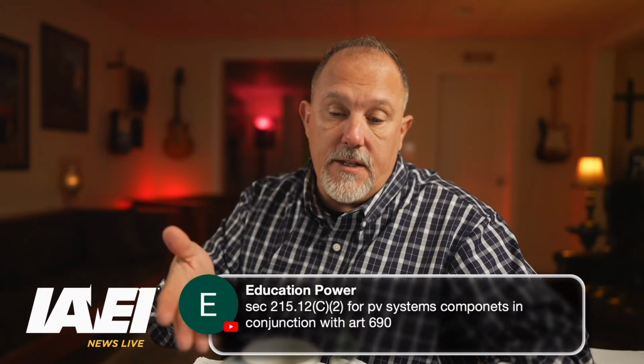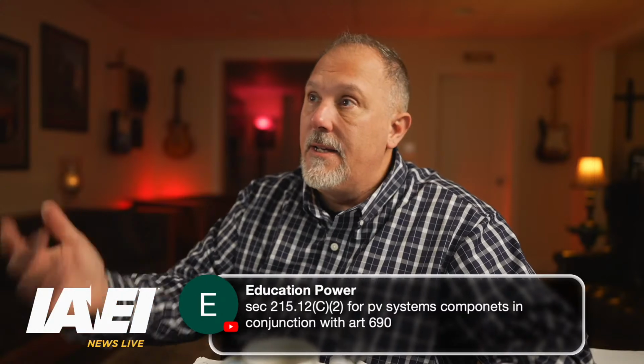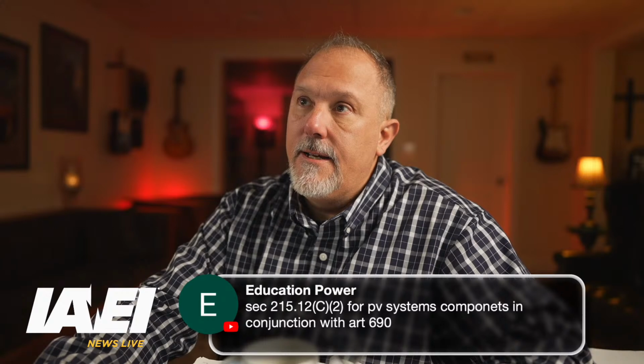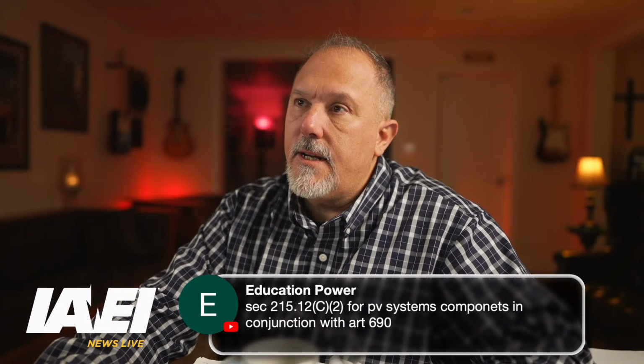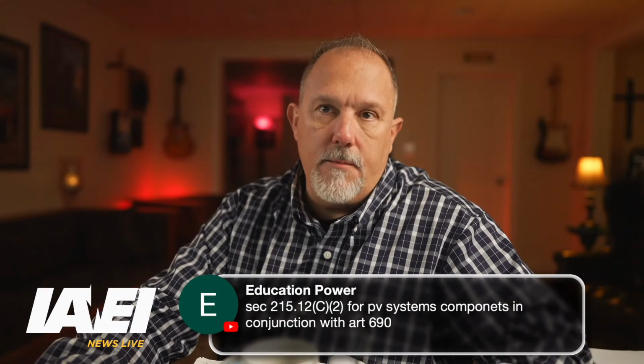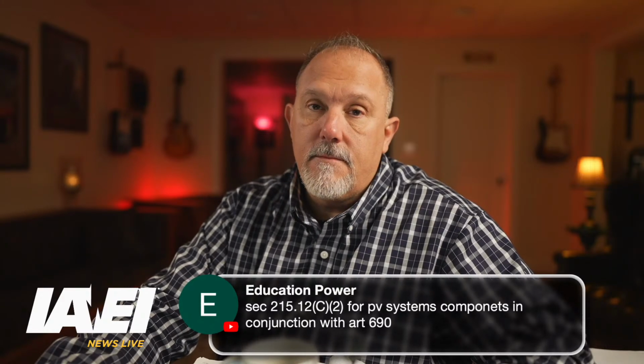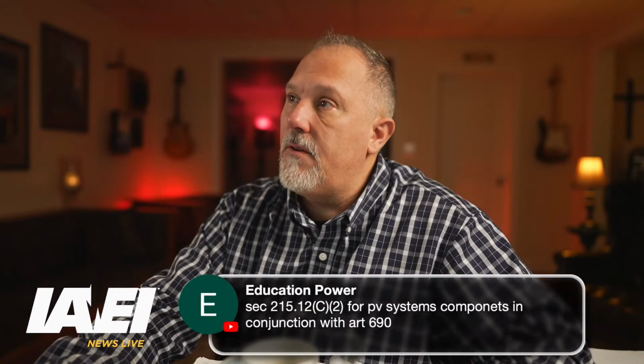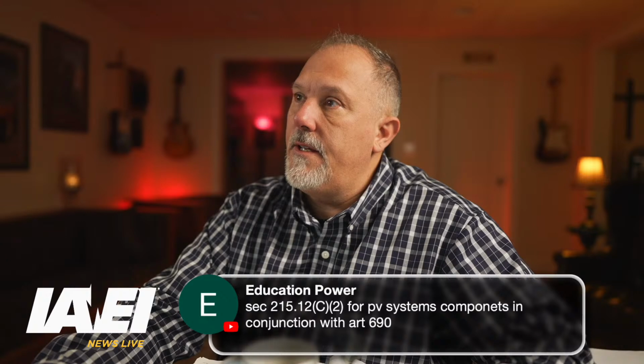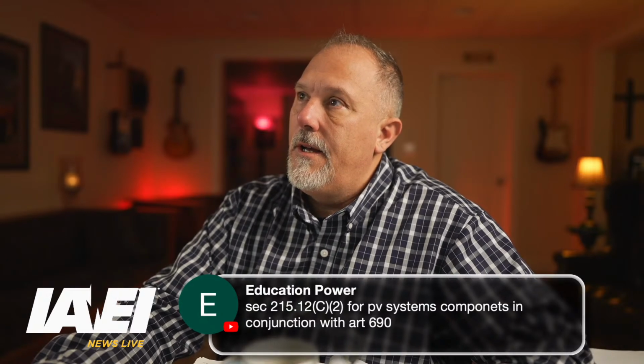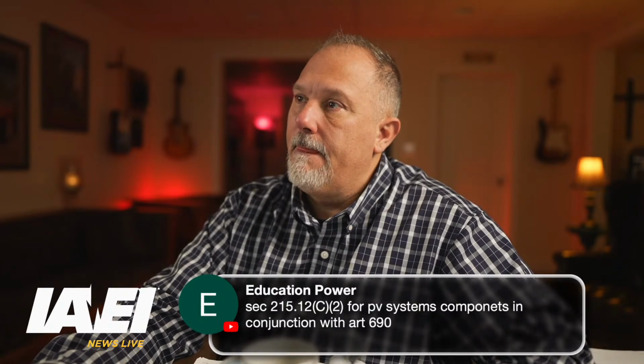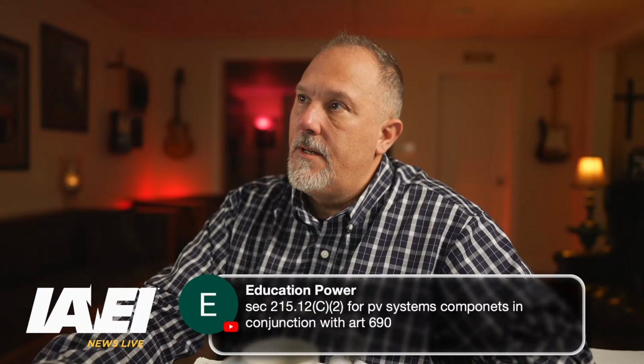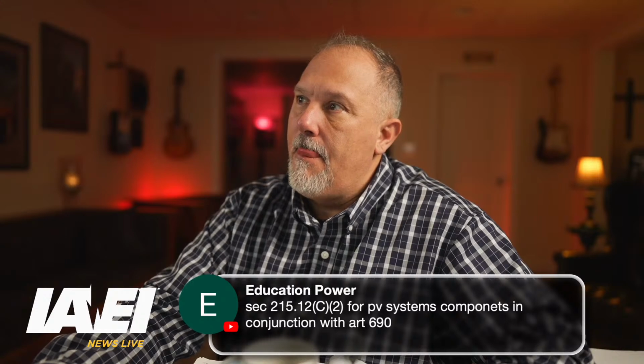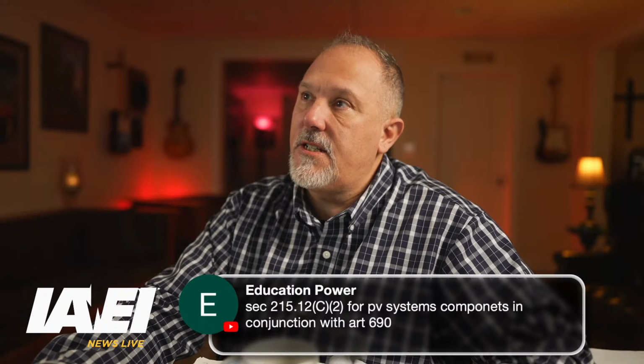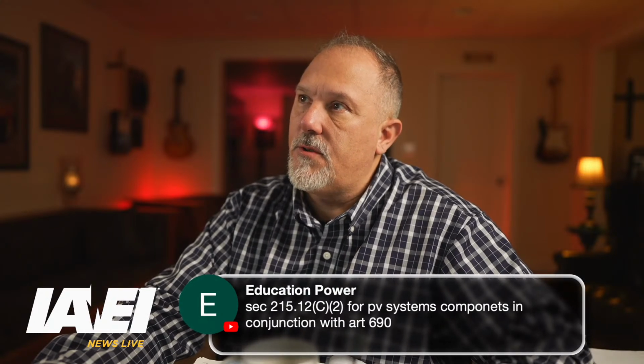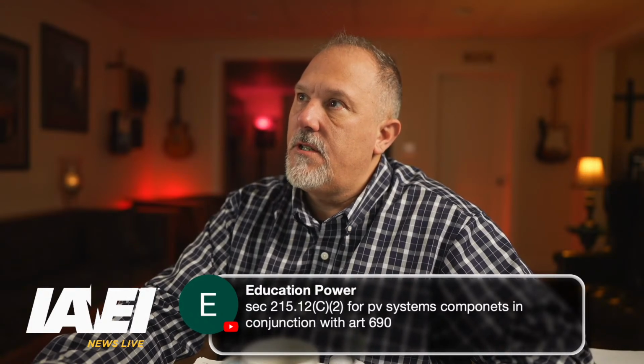I would say that 215, this would apply, and this marking would apply, but no, it doesn't apply because 690, if I go back to 690, what does 690 say? This is why creating your own terms and redefining the system is ungood. But that's never stopped Panel 4. So what they did is in 690.4, or in Article 690, I'm trying to see where they have the diagram. Overcurrent protection. PV system DC circuits. A single overcurrent device where required shall be permitted to protect the PV modules, DC for the overcurrent devices, transformers. Oh man.